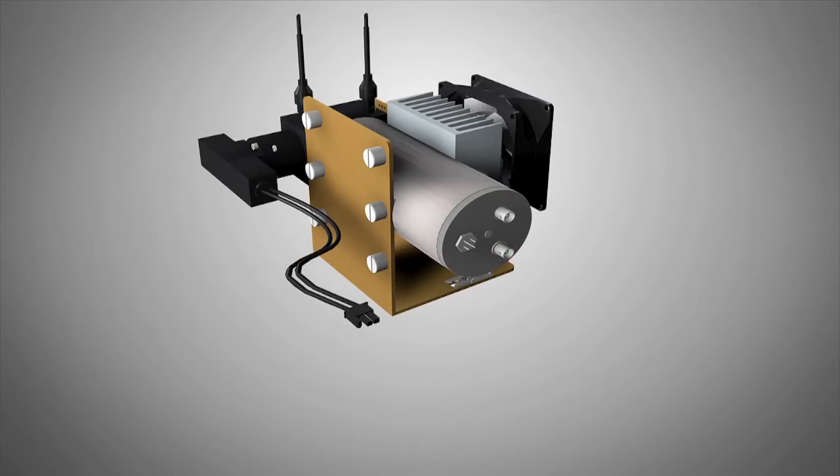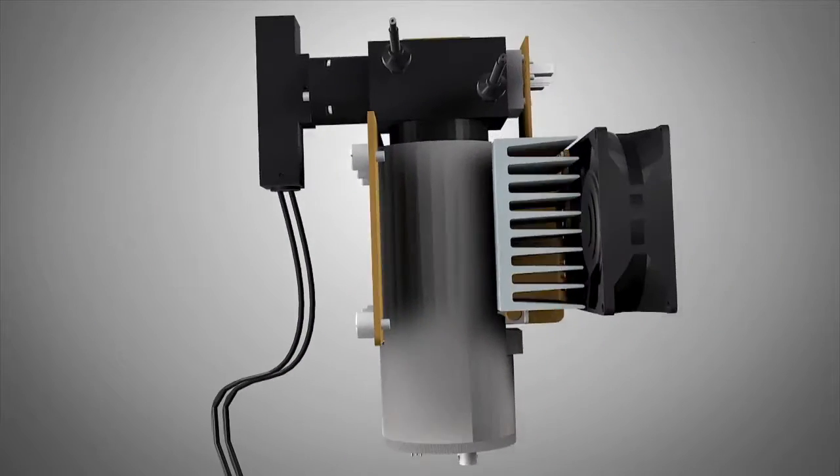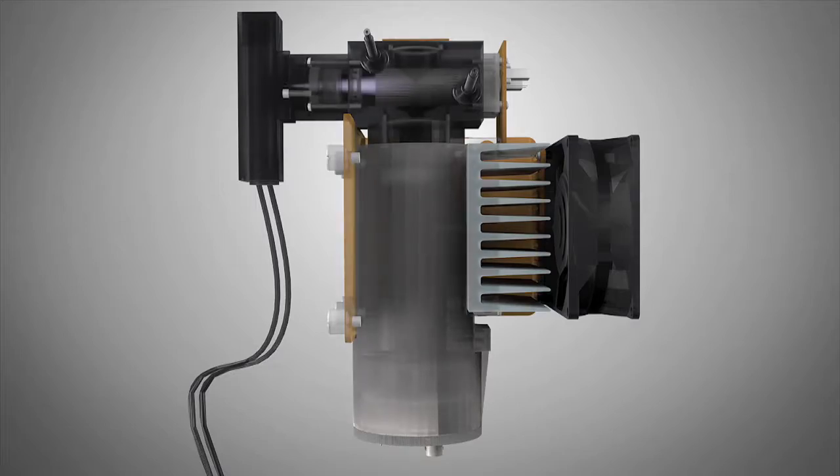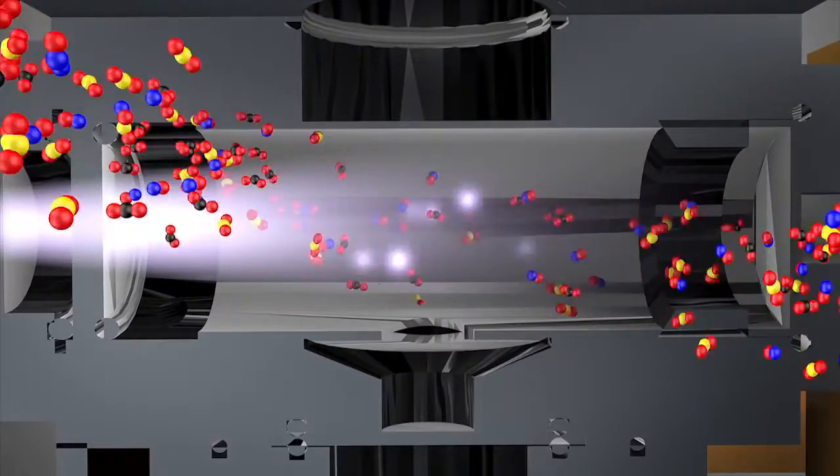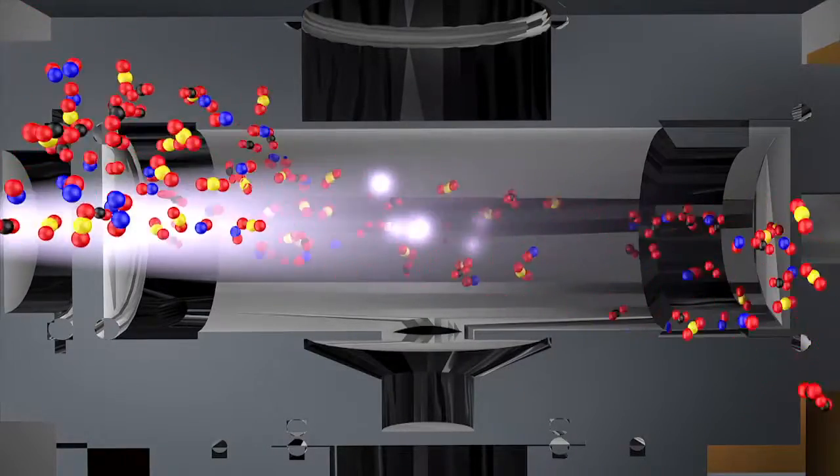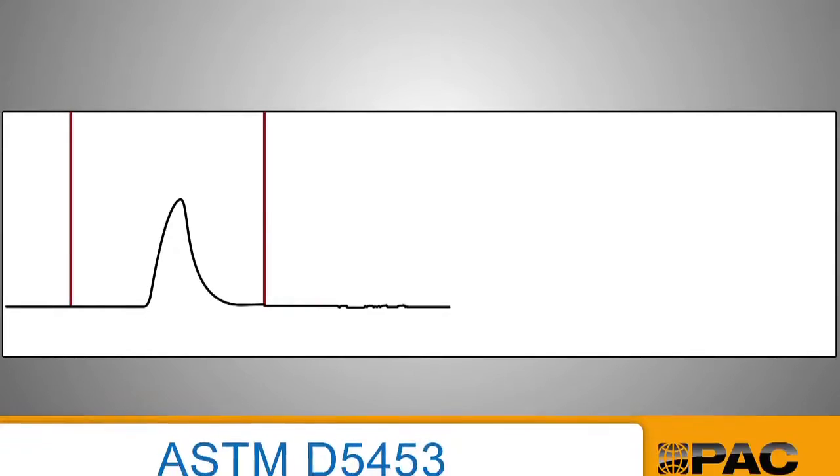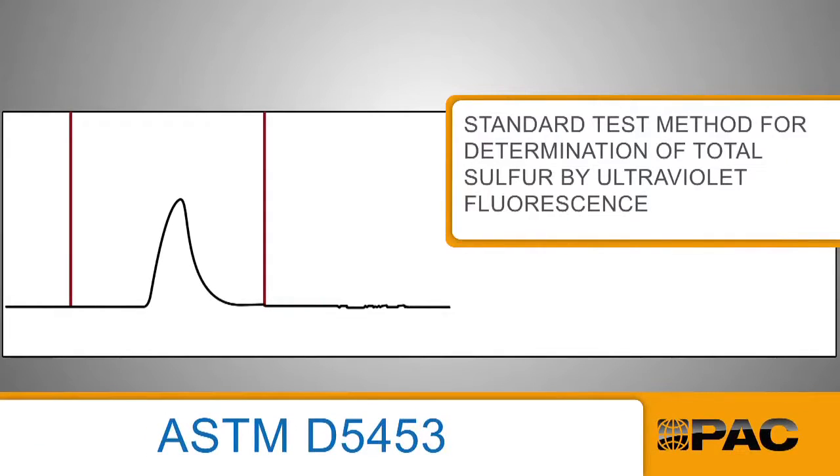The sample is exposed to ultraviolet light which excites any sulfur dioxide. Upon returning to a stable state, energy is emitted as a flash of light which is measured by a photomultiplier tube. The amount of light emitted is proportional to the amount of sulfur in the sample. The detection method is based on primary test method ASTM D5453 for high correlation to your laboratory results.